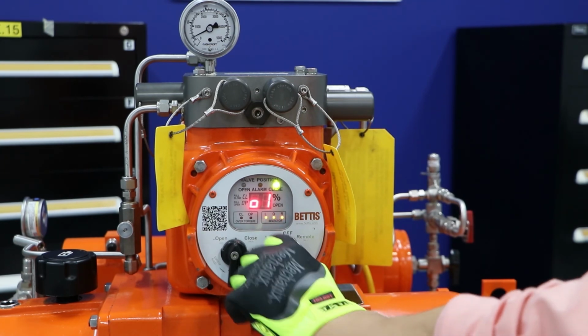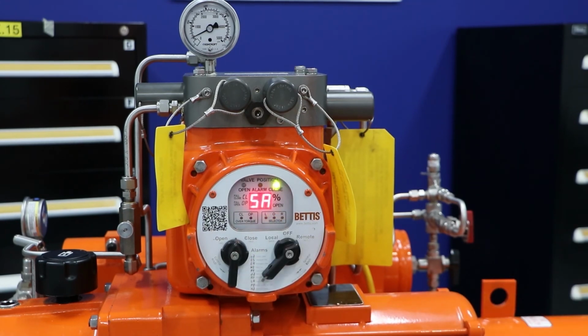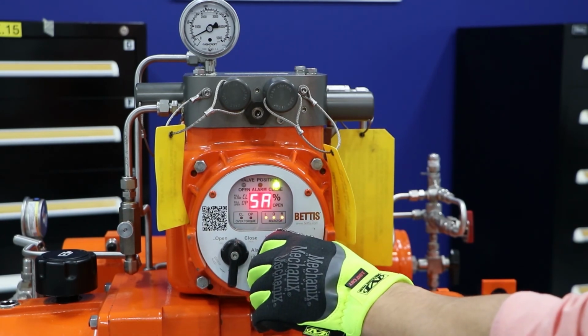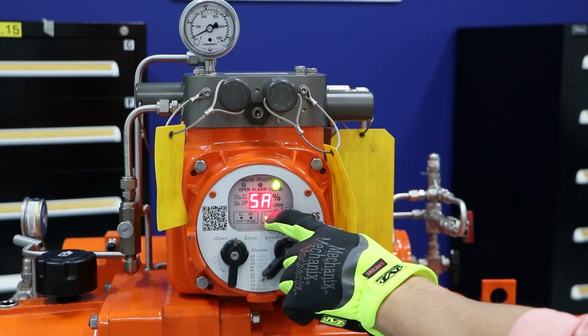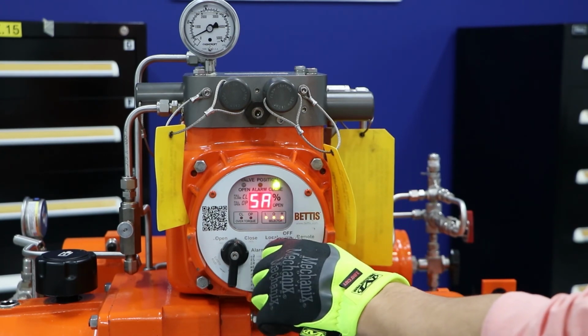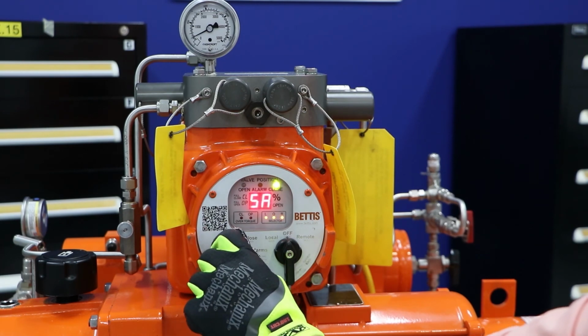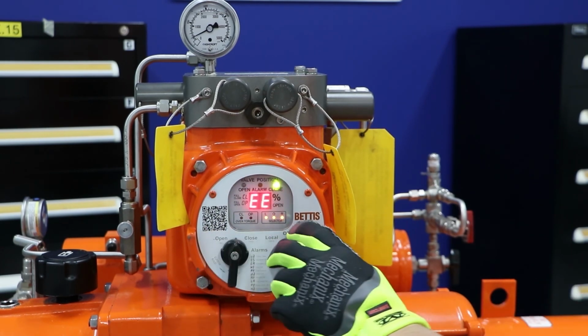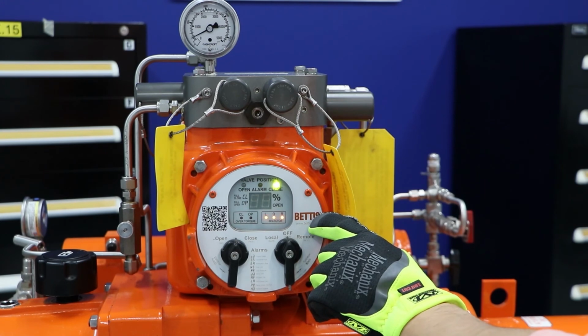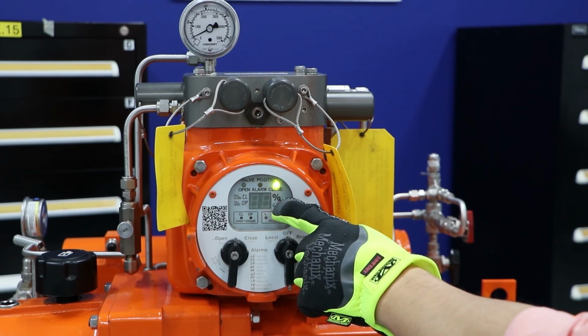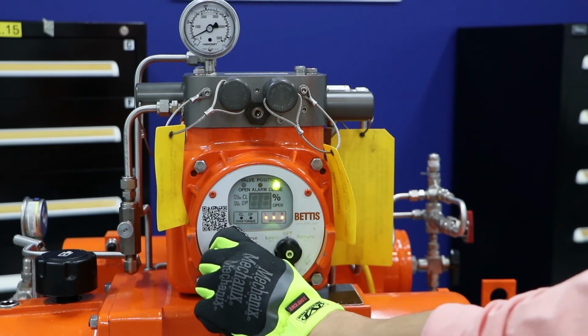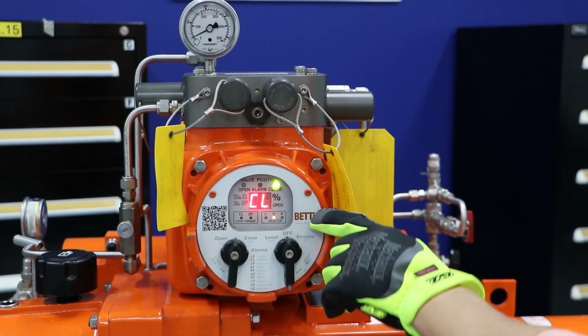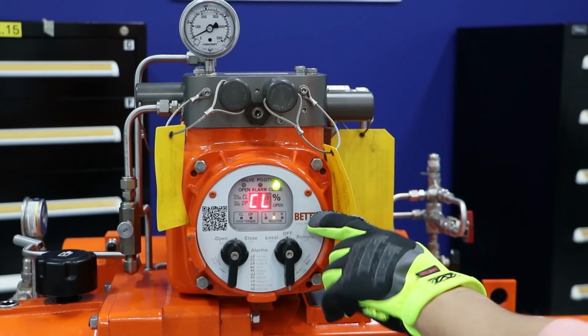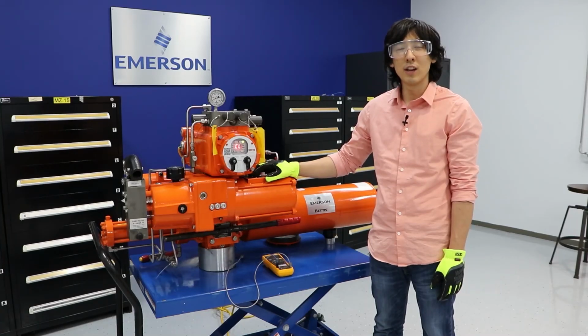So we go to Remote. We'll scroll through the screen till you see SA. SA is to save the configuration that we just did. So let's put this back in off, and we're going to toggle this yes. And that saves our calibration that we just made. Now you see EE flash here, and EE is to exit the menu. So once we hit yes, it'll return back to its normal operating state. At this point, you've successfully calibrated your analog output 1.